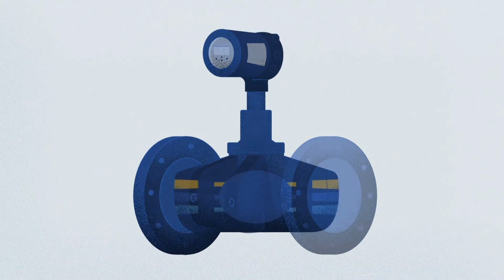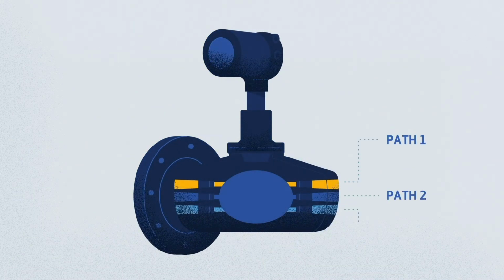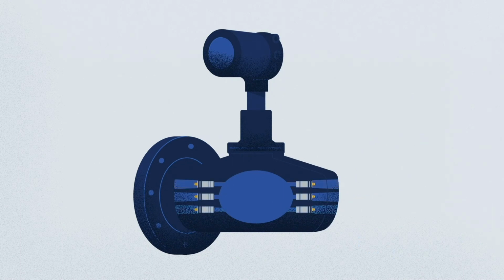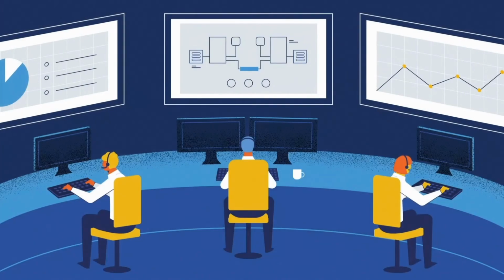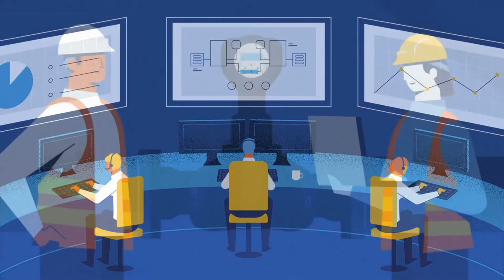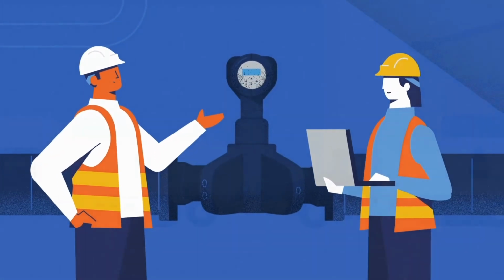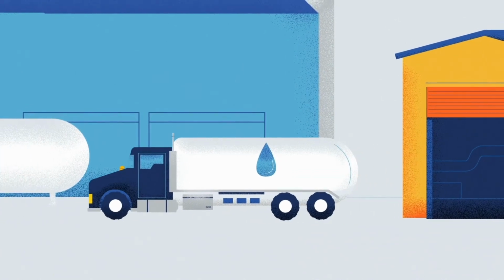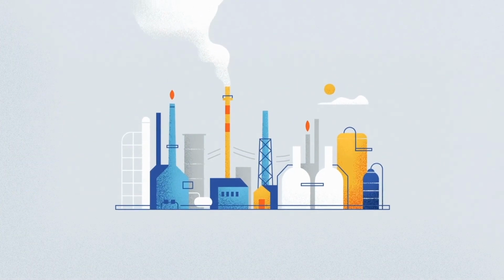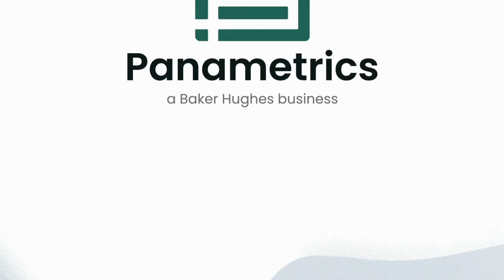The multiple-path transducer design gives them better accuracy than their old flow meter, which they need for their blending application. And if that isn't enough, the engineers can remove the ultrasonic transducers from the Panaflow meters for service or replacement without the need to shut down their process, which means less downtime, lower operational costs, and lots of money saved. It also means a happy customer.